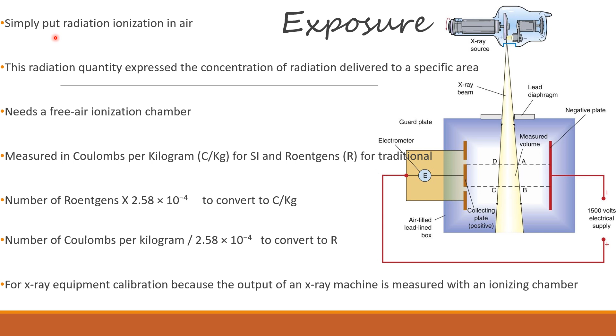The number of roentgens for exposure in air is multiplied by 2.58 times 10 to the negative 4 to convert to coulombs per kilogram. Now, if you're converting coulombs per kilogram to roentgens, it's divided by 2.58 times 10 to the negative 4. For X-ray equipment calibration, the output of an X-ray machine is measured with an ionization chamber. So again, usually physicists will come once a year and bring an ionization chamber that they hook up and place on the table, and they can measure the amount of radiation ionization.